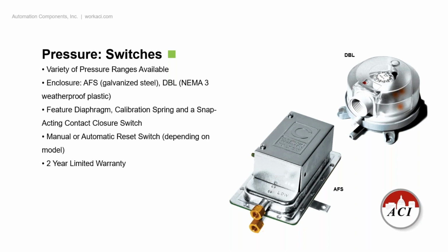We also have pressure switches. So basically it comes down to a specific inch of water column where you want that relay to switch. The AFSs are a little bit tricky in the field to know where that actual trip point is. We came out with a DBL, and what customers like about this is it actually has an arrow pointed to the screw, a knob so to speak, that you can adjust the trip point with, and that arrow will show the exact inch of water column where you want to trip that relay. Plastic enclosure on the DBL, metal enclosure on the AFS. High and low barbs showing on both.